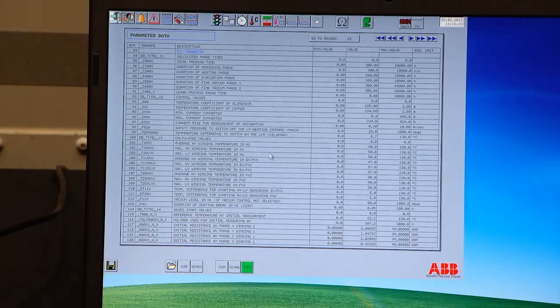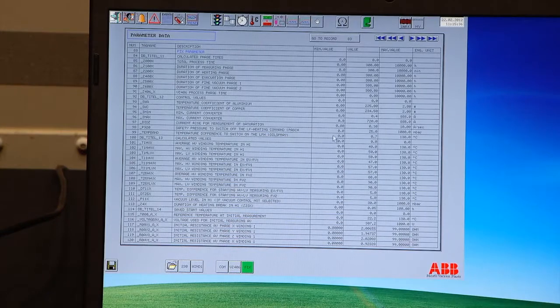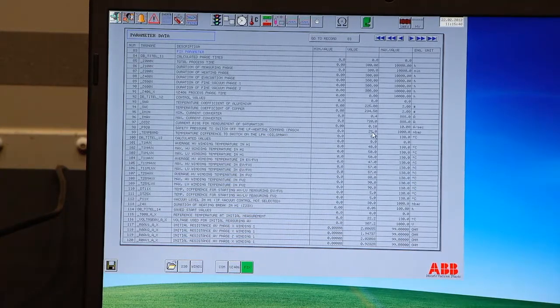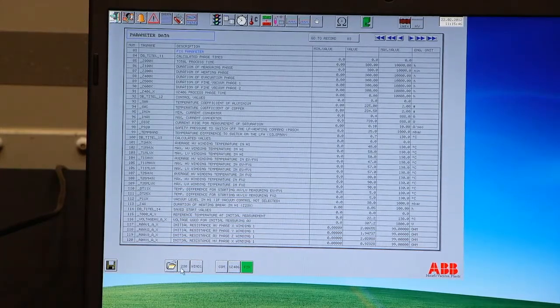One example is the minimum pressure for heating, that is called P920, safety pressure to switch off LFH heating command. That is set to 25 millibar, and that you cannot change. That is to avoid flashover scenarios. You cannot go lower than that and heat. LFH will not start.